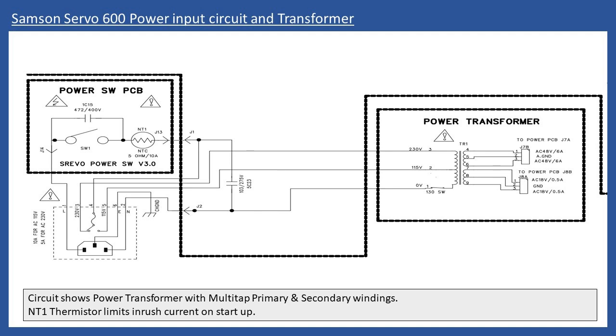Now, just remaining on the circuit schematic here for the Samson Servo 600, you can see where it says power transformer, where you have the primary windings, but then you have multiple dual secondary windings. The bit that I want to draw your attention to is that when we talk about the VA rating, or the volt-amps rating of the transformer, often what we're referring to there is the higher current requirements. So here you can see for the power amplifier, it's rated at 6 amps. And then for the low voltage type supplies, it's rated at 0.5 amps. Now the transformer manufacturer will design the transformer depending on what the load requirements are. But just to be aware of that, all right?